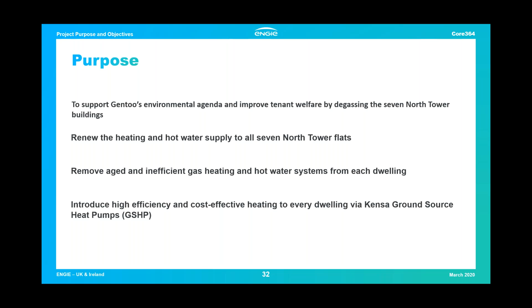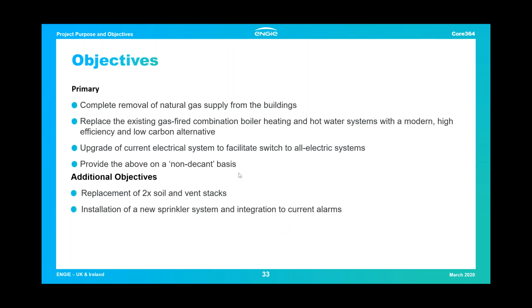So the objectives, as briefly covered, were removal of natural gas from the buildings, replacing all gas-fired combination and hot water systems with a low carbon alternative. To do so, we had to upgrade the current electrical systems to facilitate a switch to an all-electrical system, since the base supplies into the buildings weren't large enough to cope with the additional demand. And all of this was to be delivered while customers were living in their homes. They also took the opportunity to add some additional scope of works for safety measures, predominantly new sprinkler systems and upgraded fire alarms, giving customers that ultimate feel-safe factor, plus replacing some soil vent pipes while working in the home. So there's a full array of work going on while carrying out this project.